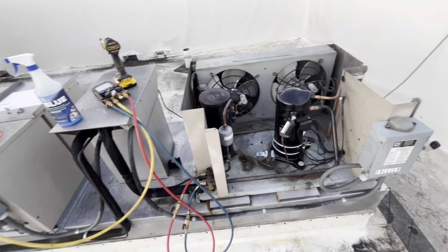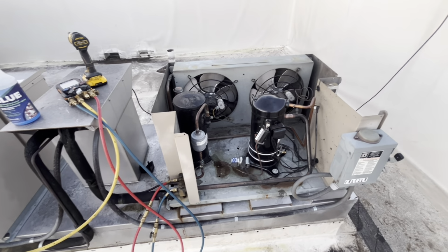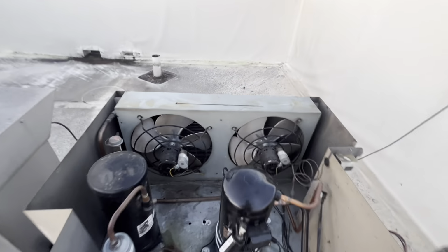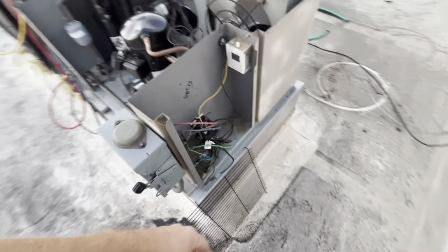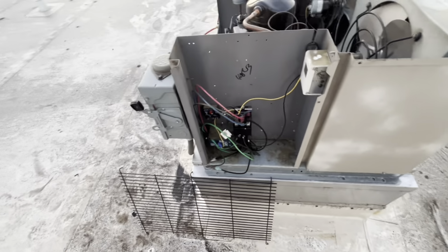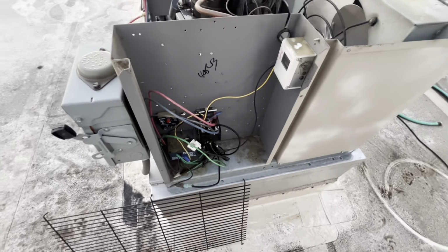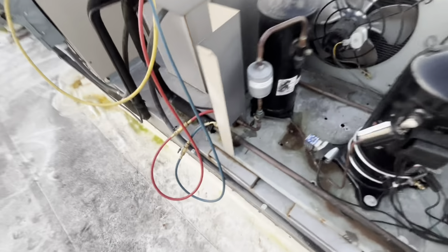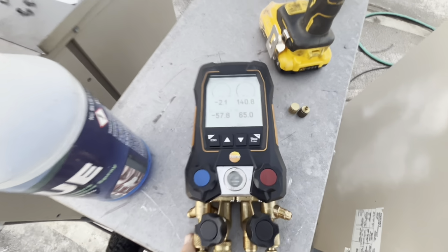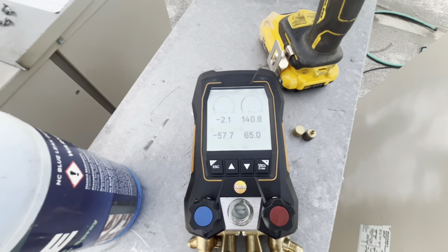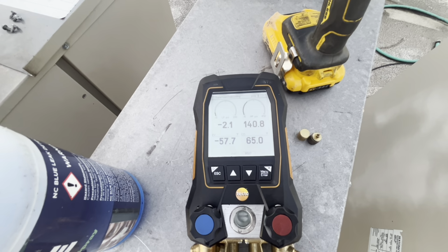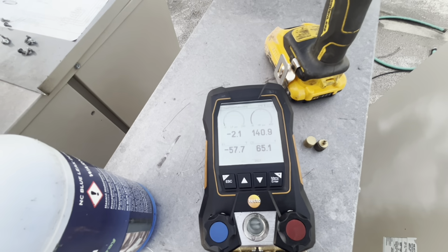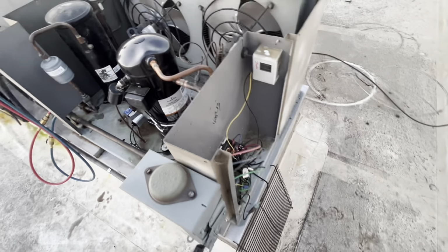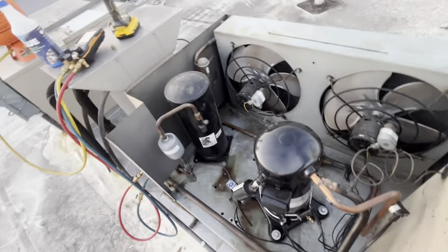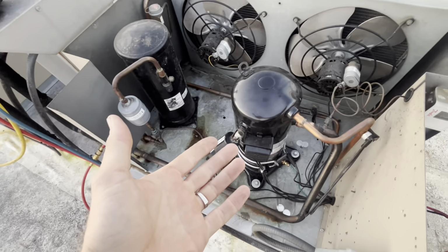So the assumption was that we would be low on gas since the fans were running, right? We weren't off on a high pressure system. I'm the only one here. I can't get inside at this location, but currently my only assumption has to be that it's satisfied, because the solenoid's closed inside. So either the thermostat has no power or she's satisfied. And my unit has power because I can bump my contactor and she runs. But I can't do anything because the solenoid downstairs is closed.